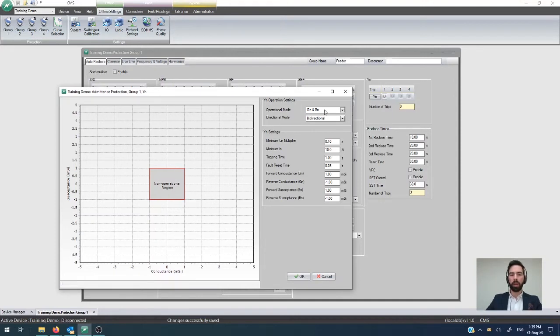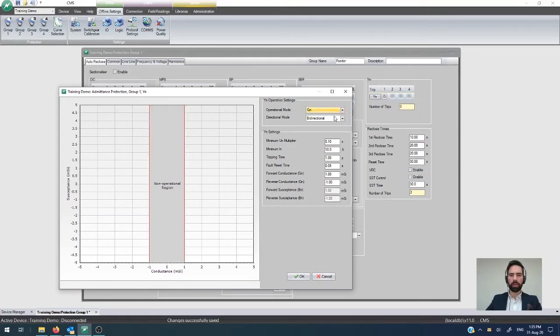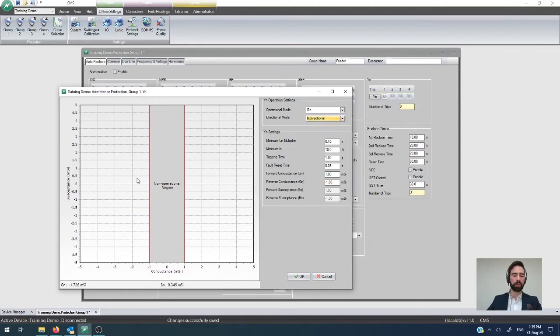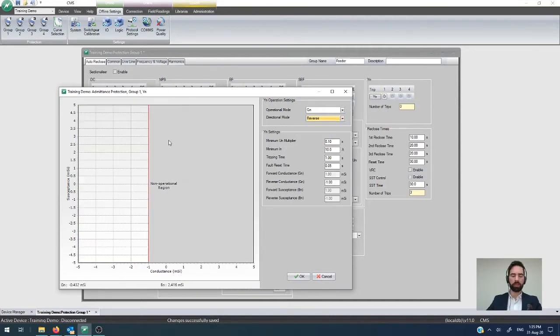If you wanted it to operate only on conductance so you're looking at resistive components only then you can do so by setting that to GN and changing the directional mode either from being bi-directional where you don't mind whether it's in the forward or reverse direction or only in the forward direction so you have a non-operation region like this or only in the reverse direction like so.